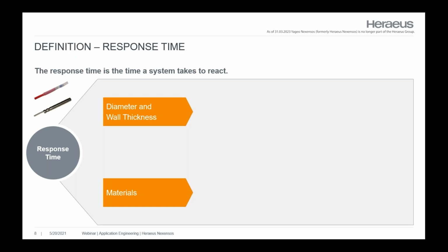You can see here an example in the pictures on the top left. Here it depends really on the way of mounting. I want to point out two main factors that influence the response time: on the one hand, the diameter and the wall thickness, and on the other hand, the materials. By material, I mean the material of the housing itself and also the filling material.